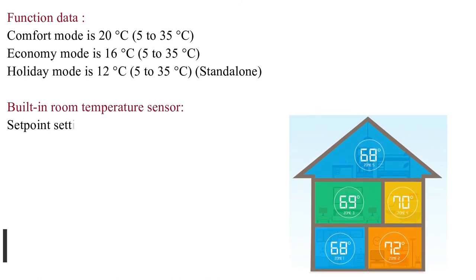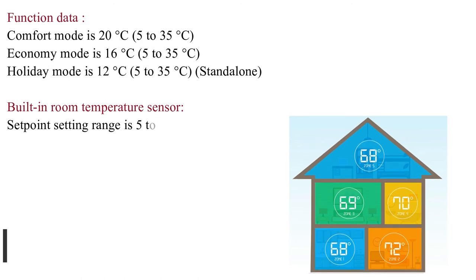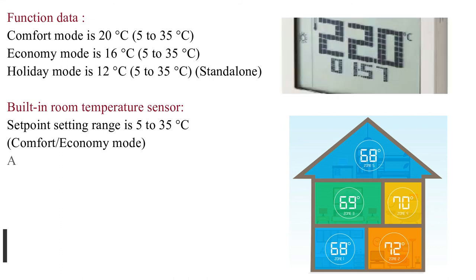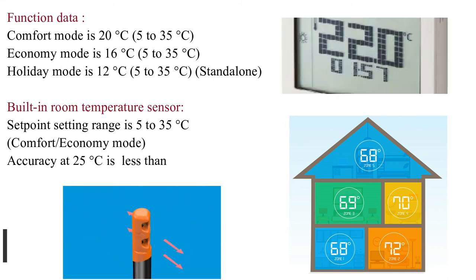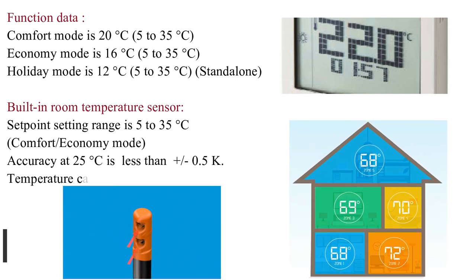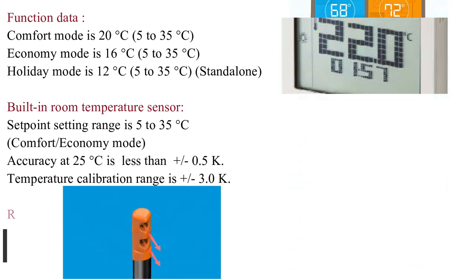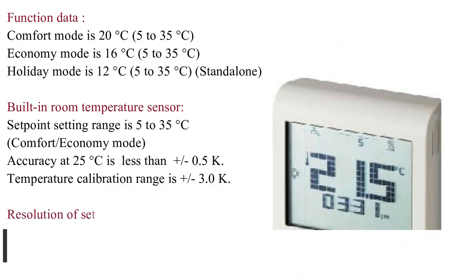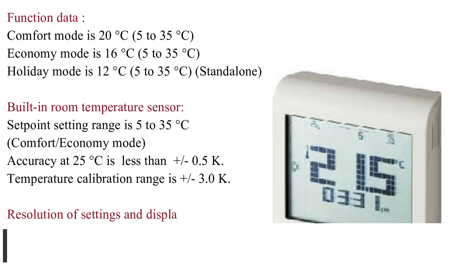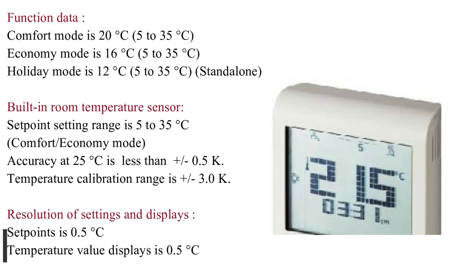Built-in room temperature sensor: Setpoint setting range is 5 to 35 degrees Celsius for comfort and economy mode. Accuracy at 25 degrees Celsius is less than ±0.5 K. Temperature calibration range is ±3.0 K. Resolution of settings and displays: Setpoints is 0.5 degrees Celsius, temperature value displays is 0.5 degrees Celsius.